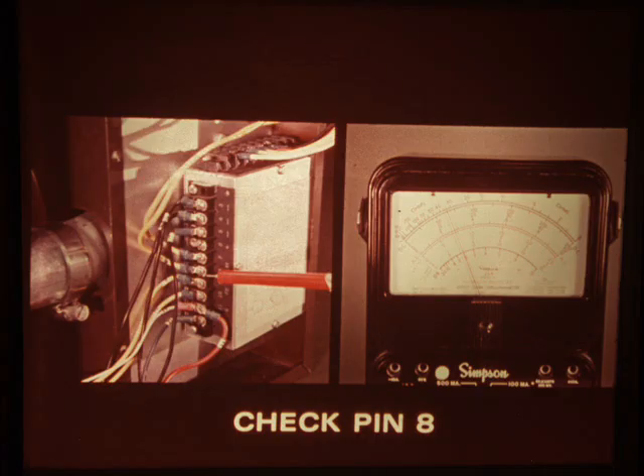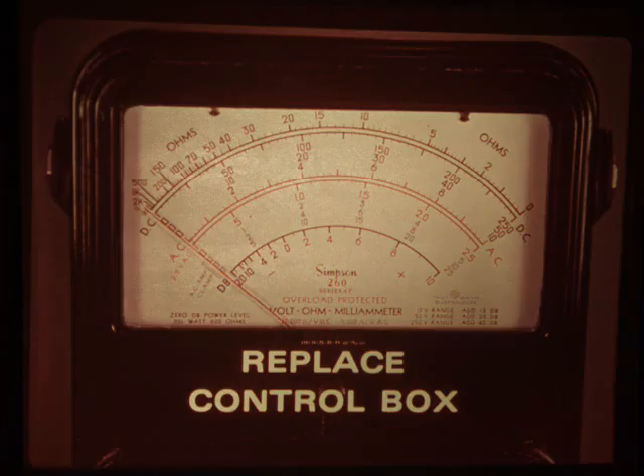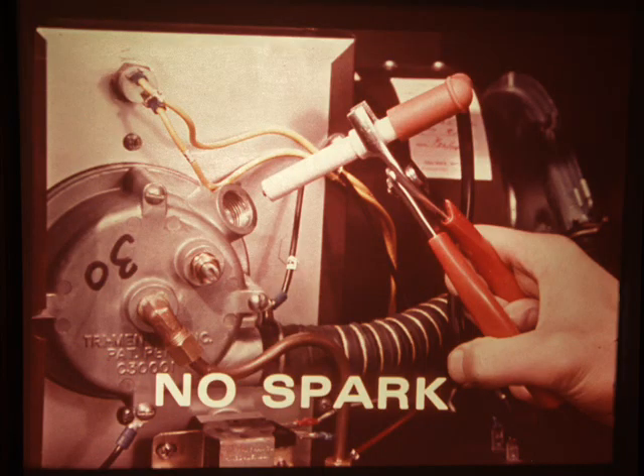If there's no voltage at pin 11, check the voltage at pin 8 to ground to be sure there isn't an open high limit switch. If the switch is okay, but you can't get voltage to the circuit, replace the control box. Let's backtrack now to our original checks in the coach. Let's see what to do if there was no spark at the igniter tip.